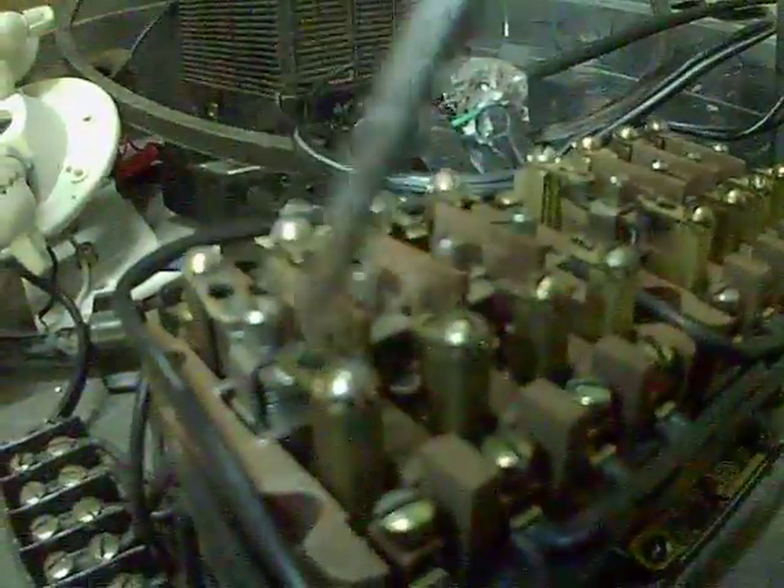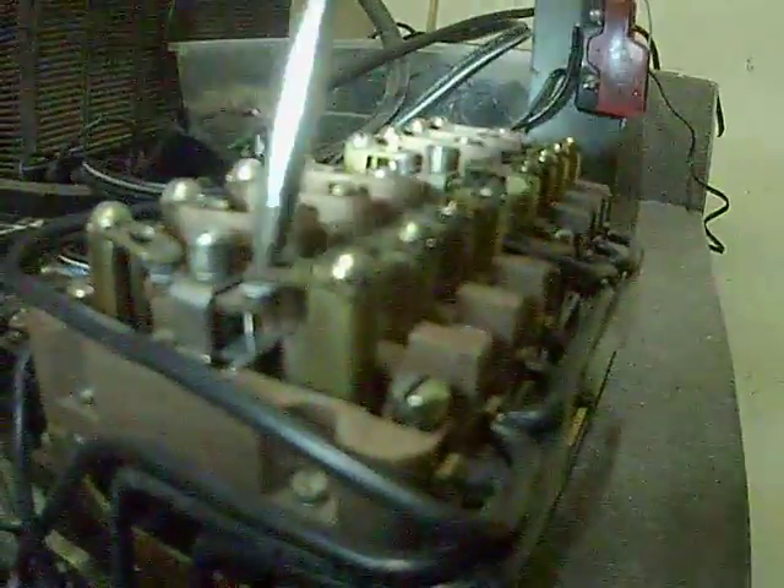See, these ones are normally closed and these are normally open. But right in here these things are getting corroded, and their spring was getting worn out so it wasn't popping up and contacting.